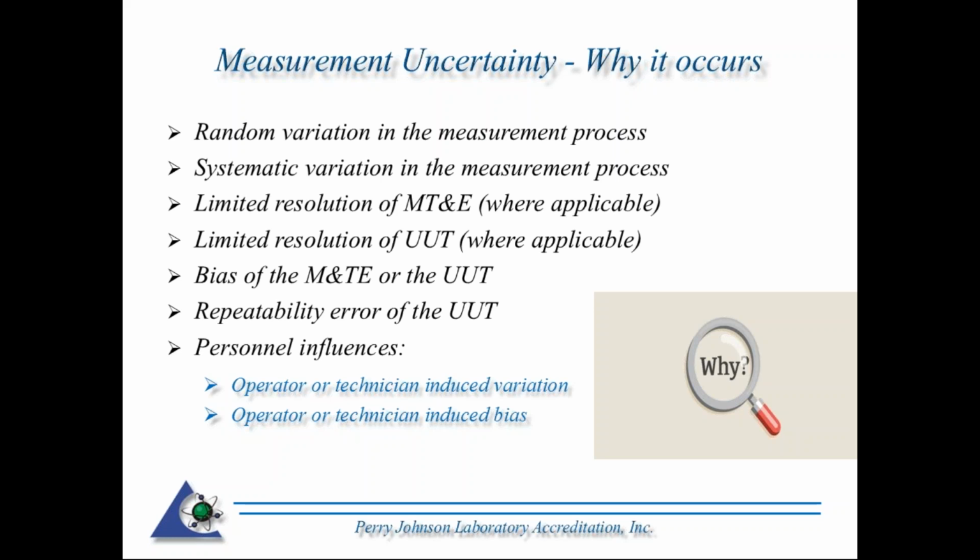We can have influences by the folks or personnel that are taking the measurements. You can have operator or technician induced variations, operator or technician induced biases. For the last one, I like to give the example of reading a precision flask where you're reading the meniscus, and some folks will constantly see the meniscus perhaps a little bit higher or a little bit lower than what others are reading it as. That would be considered a bias.